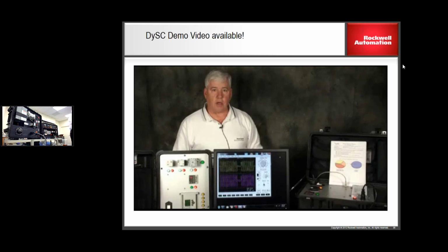Think of an encoder. There's a lot of lines out there with an encoder on it. Which bottle's going to get knocked off? Which tire's going off? Oops, the encoder just went down. Controls probably going to stop the whole line until you figure out why the encoder went down. Somebody's going to troubleshoot that encoder and drive themselves nuts trying to find the problem. Again, it's 70 milliseconds, would the lights even have blinked? Probably not.